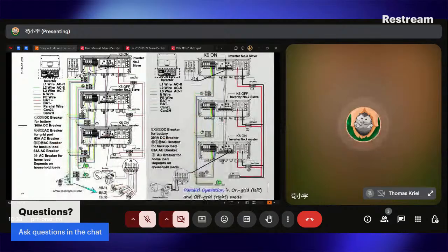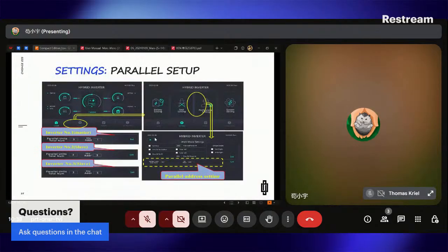And here is the wiring of the whole system when you parallelize them. It looks complex, but don't worry. We have a detailed instruction in our user manual, and we also have an SOP so that our partners can check it. And then it's about the settings when you are in parallel. We need to go to professional settings, and if you have 3 inverters, we need to input 3 in the parallel units total number. And for the 3 inverters, the inverter addresses should be 1, 3, 5. So if you have 5, then it should be 1, 3, 5, 7, 9, and then it will work.